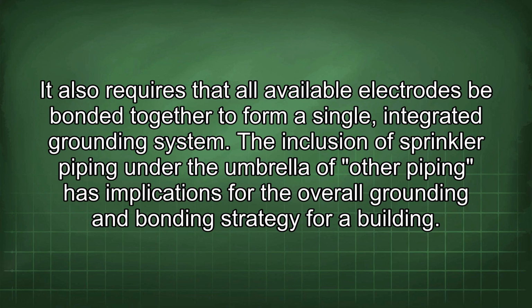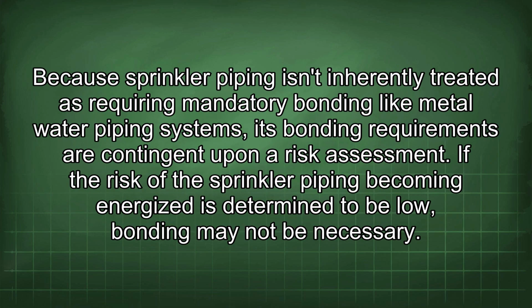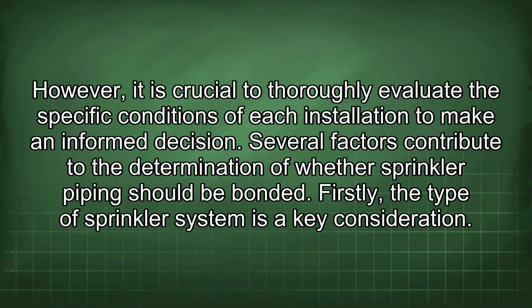The inclusion of sprinkler piping under the umbrella of other piping has implications for the overall grounding and bonding strategy for a building. Because sprinkler piping isn't inherently treated as requiring mandatory bonding like metal water piping systems, its bonding requirements are contingent upon a risk assessment. If the risk of the sprinkler piping becoming energized is determined to be low, bonding may not be necessary. However, it is crucial to thoroughly evaluate the specific conditions of each installation to make an informed decision.